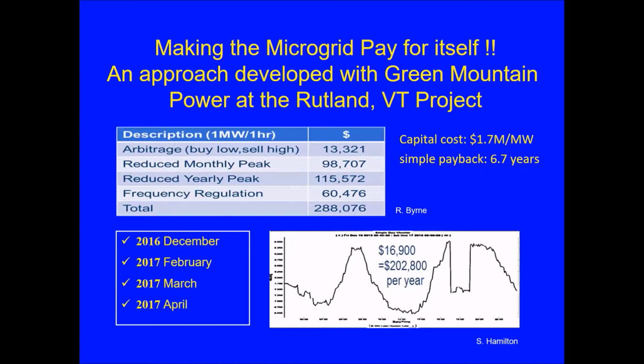And if you look at this little glitch here, or this little depression, that was when the monthly peak occurred. And at this monthly peak, the battery was well charged, and they basically provided everything the battery had in it. And this reduction in peak resulted in a savings of $16,900. And if you multiply that with 12, you get about $202,000 per year.